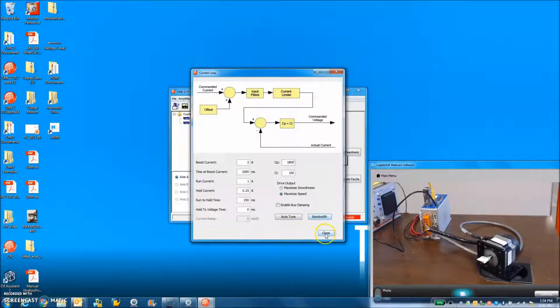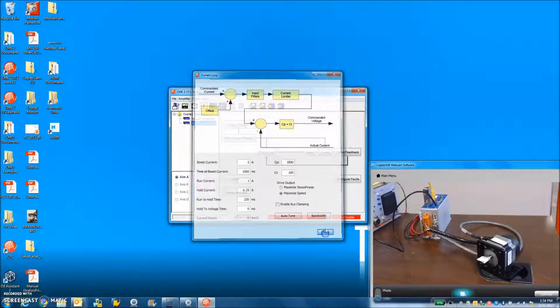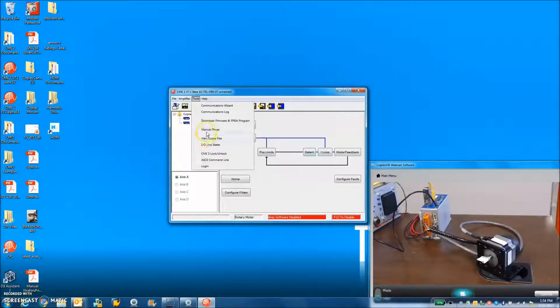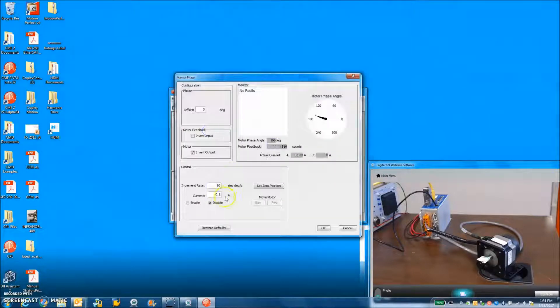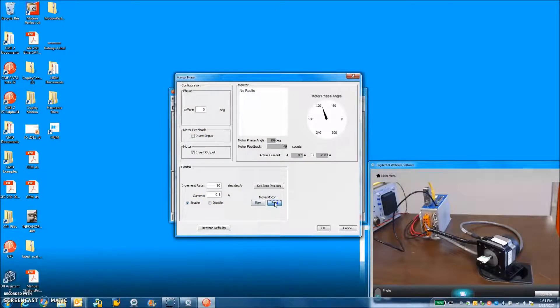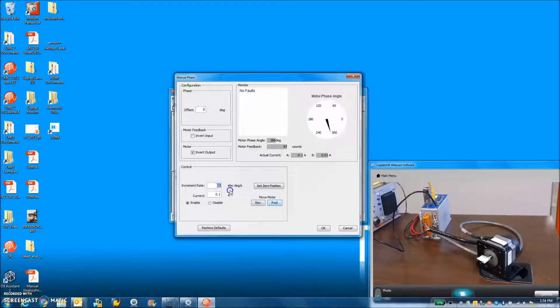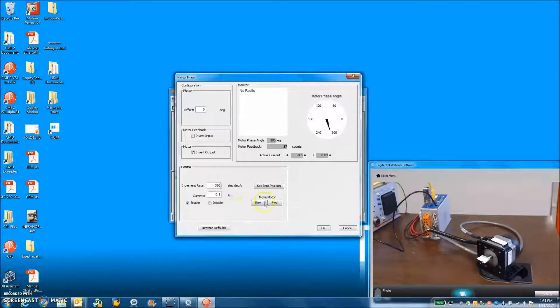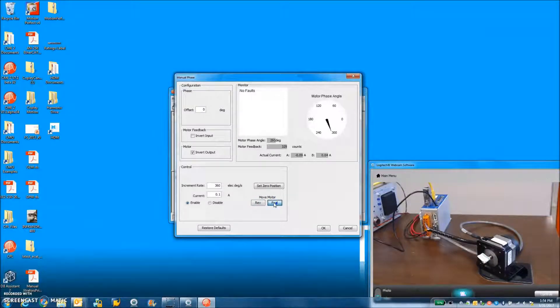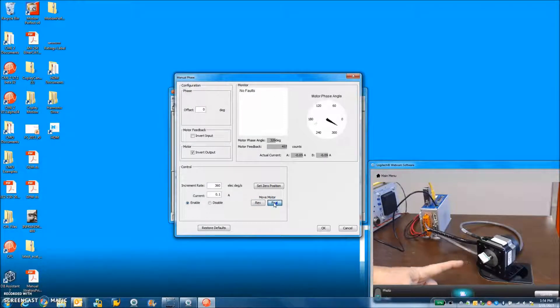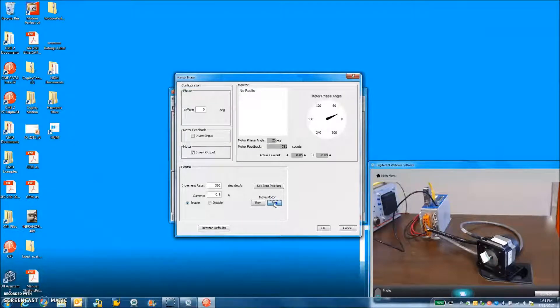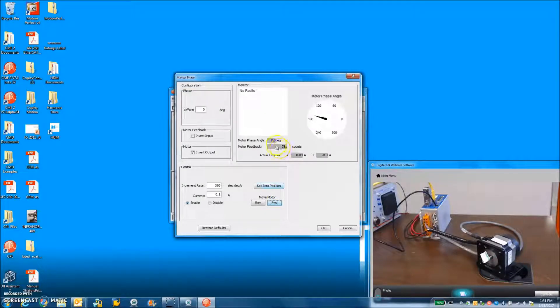I calculated the initial tuning values and came up with some currents here. The bandwidth check was a little low, so I had to auto-tune it. Actually, the first thing we did here was enable it and rotate the current vector to make sure we got the right forward direction. This is the first time you get a motor. You've got to rotate it.